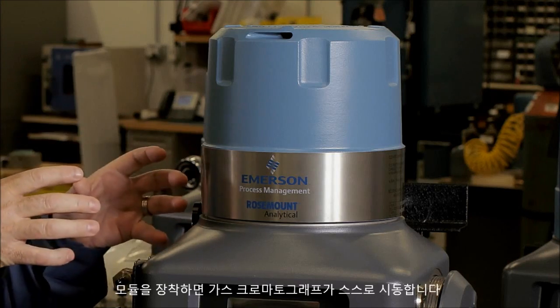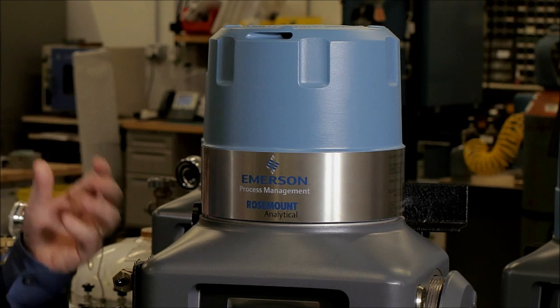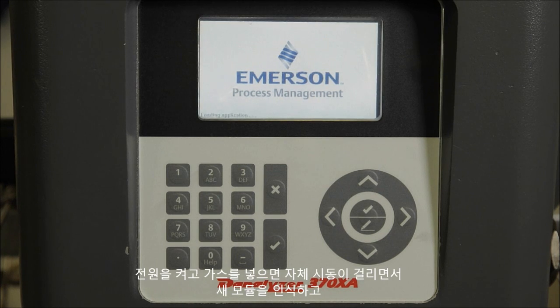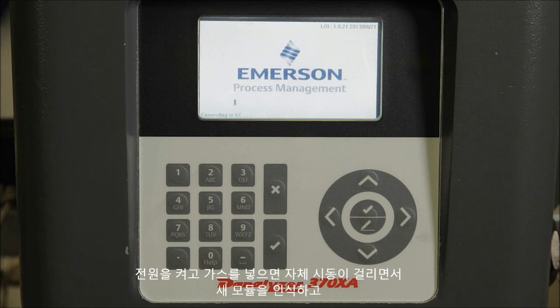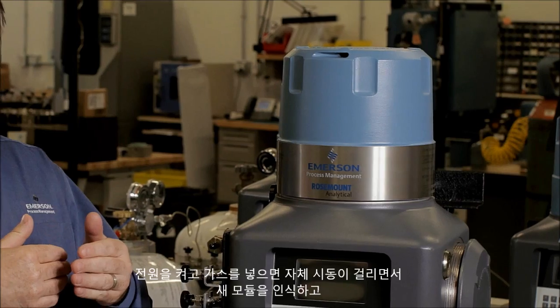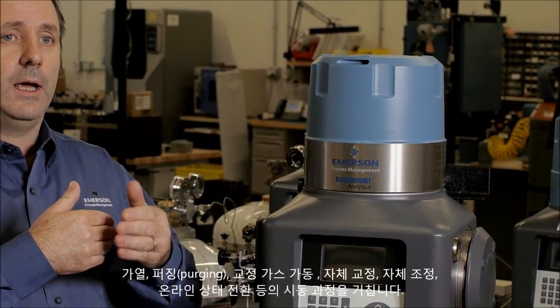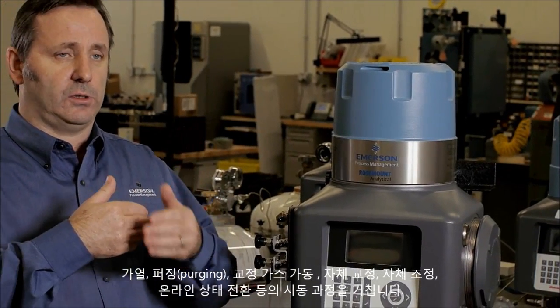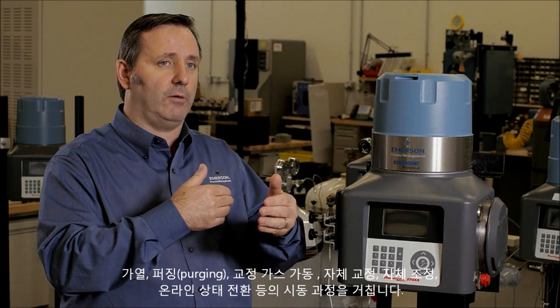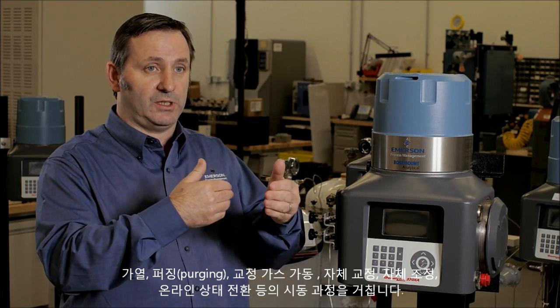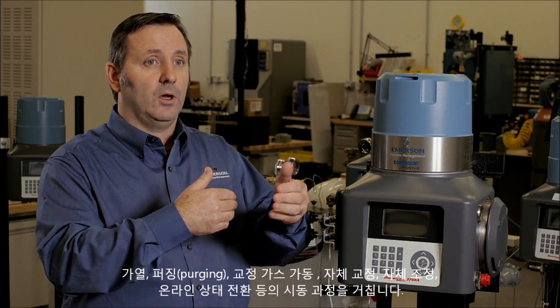Once the module is on, the GC actually starts itself up. Once you put power on there and put the gases back on, it starts up, looks at the module, recognizes there's a new module, and goes through the startup process of heating up, purging, running calibration gas, calibrating itself, maybe even making adjustments itself, and then goes online without the user having to push a button.